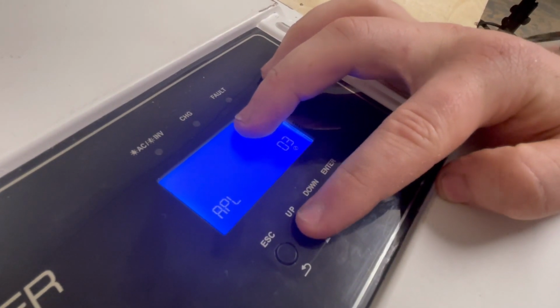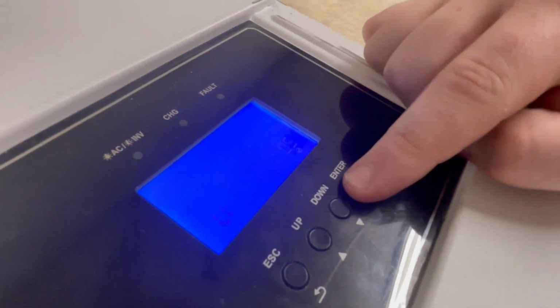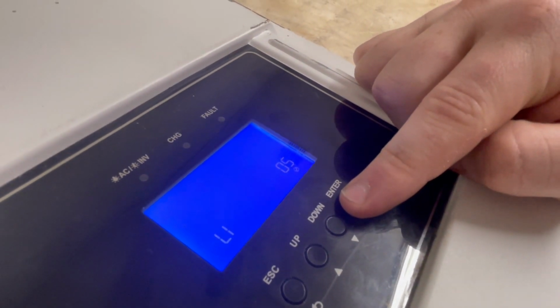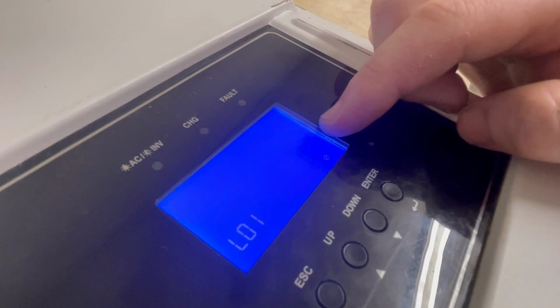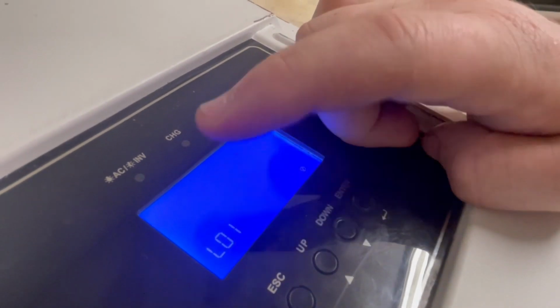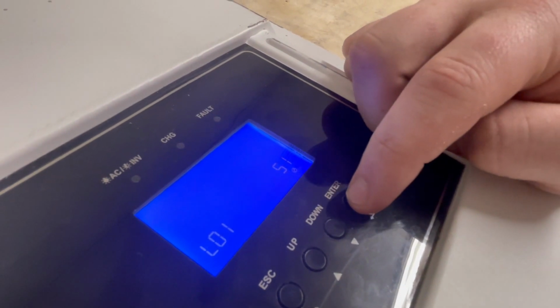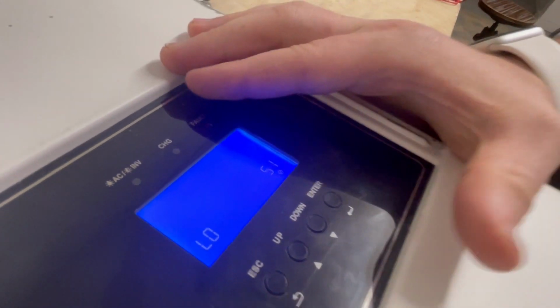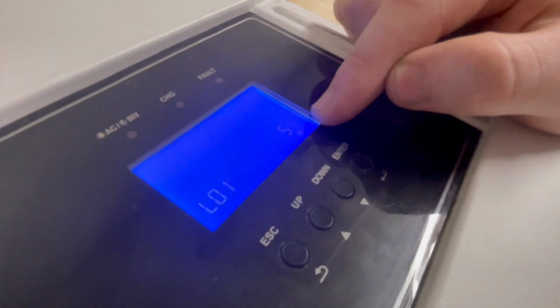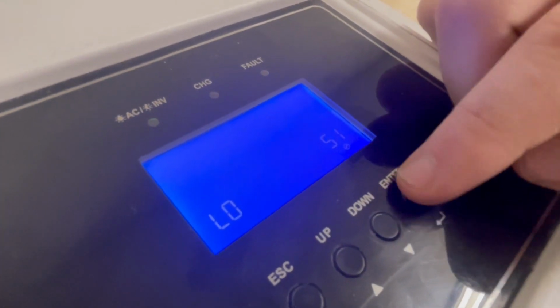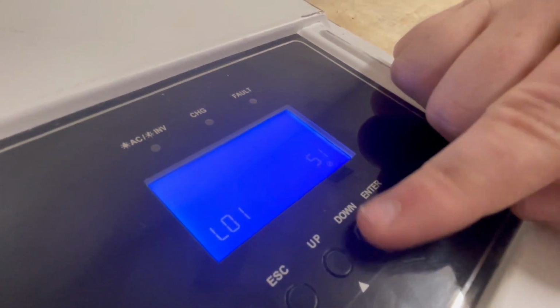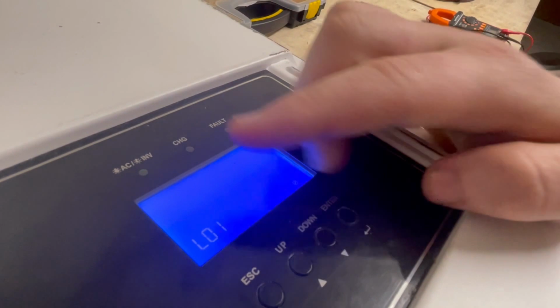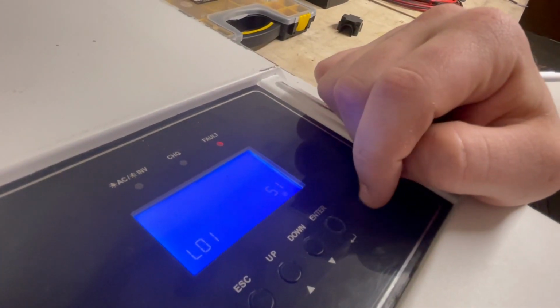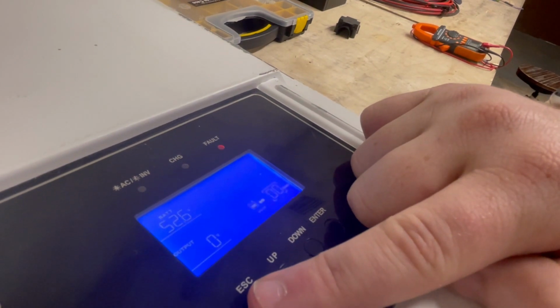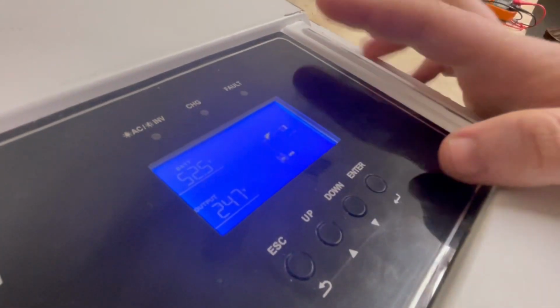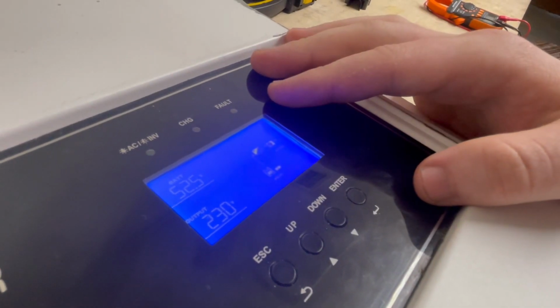and you go up to setting 5, my battery setting is lithium. So by default, it's probably not, but if you go set it to lithium, you then get to a screen that has your protocol number and then your actual setting number. We want it set to LO1. That's the only one that will work. Now on the 5 kilowatt, you're looking at the protocol being 36 on the side instead of 51. This protocol number isn't changeable. As you can see, I try to adjust it, it won't adjust. So it just happens to be there. And we've changed it, and it took the setting, and we're communicating.